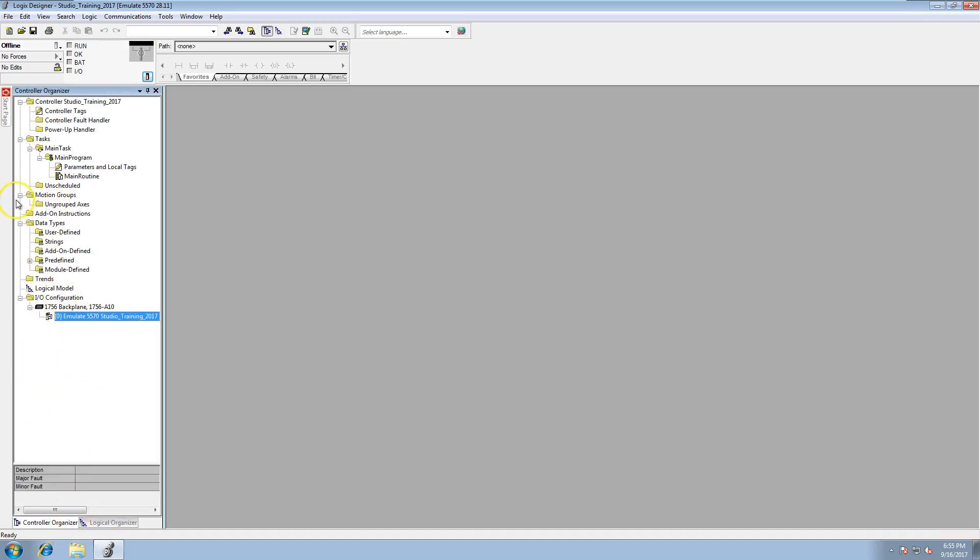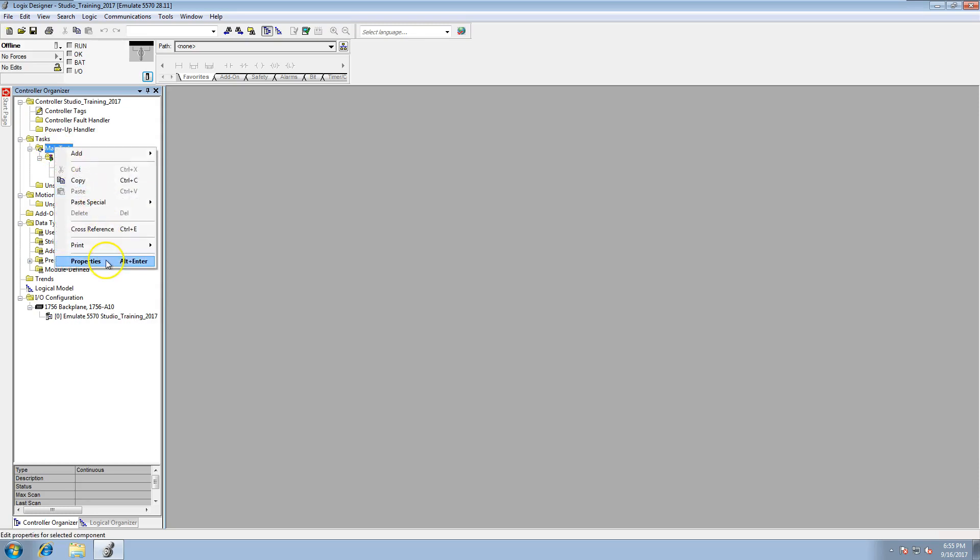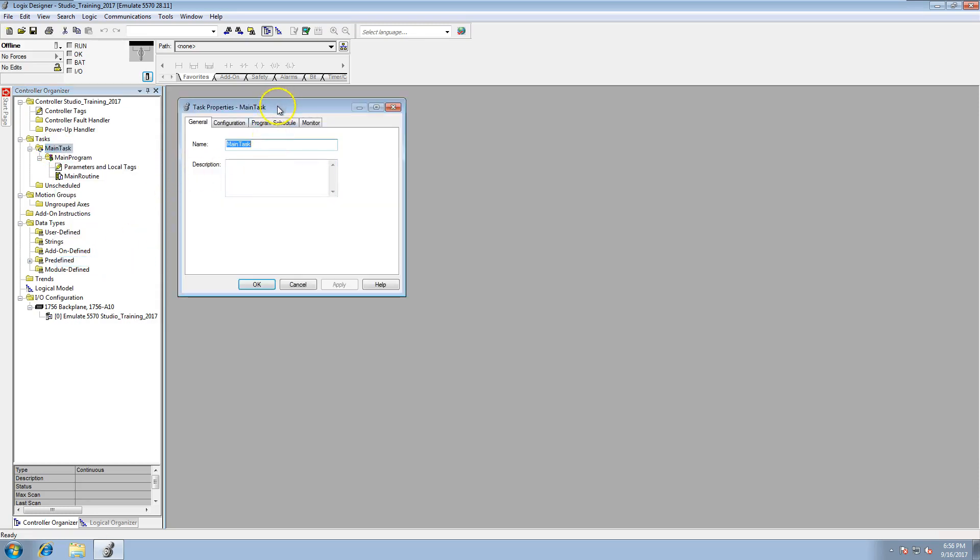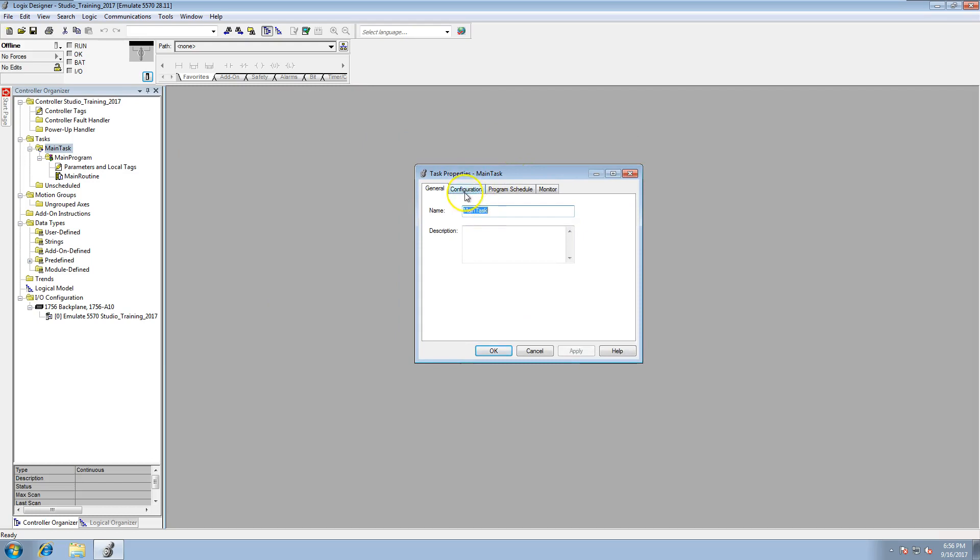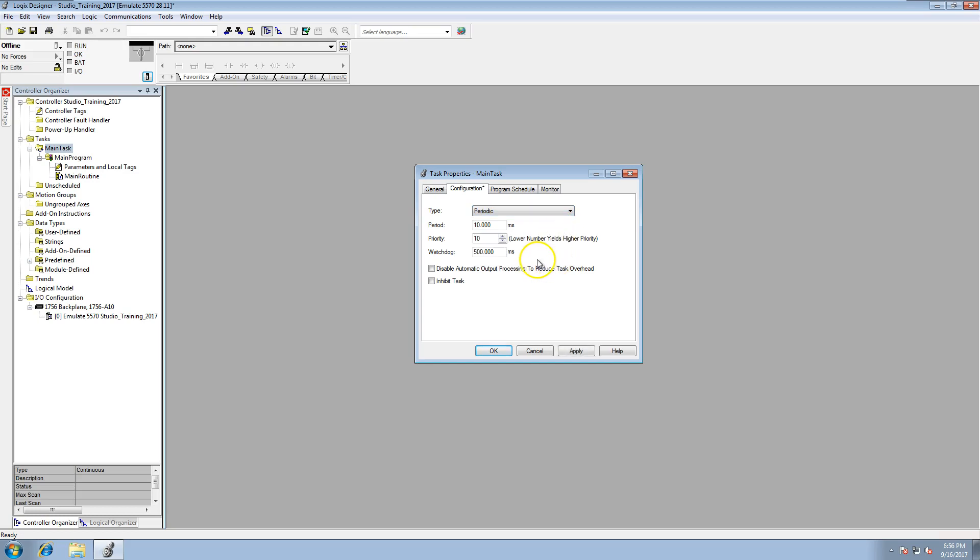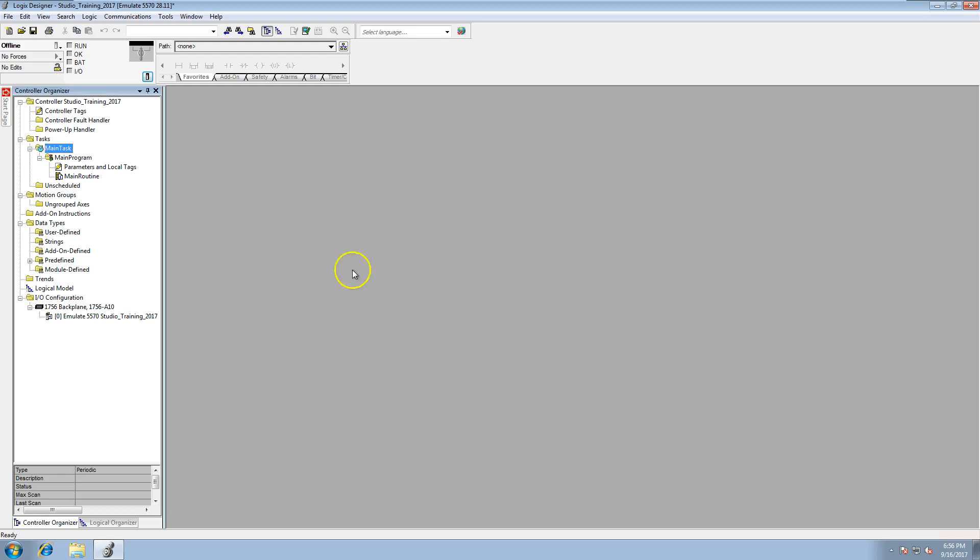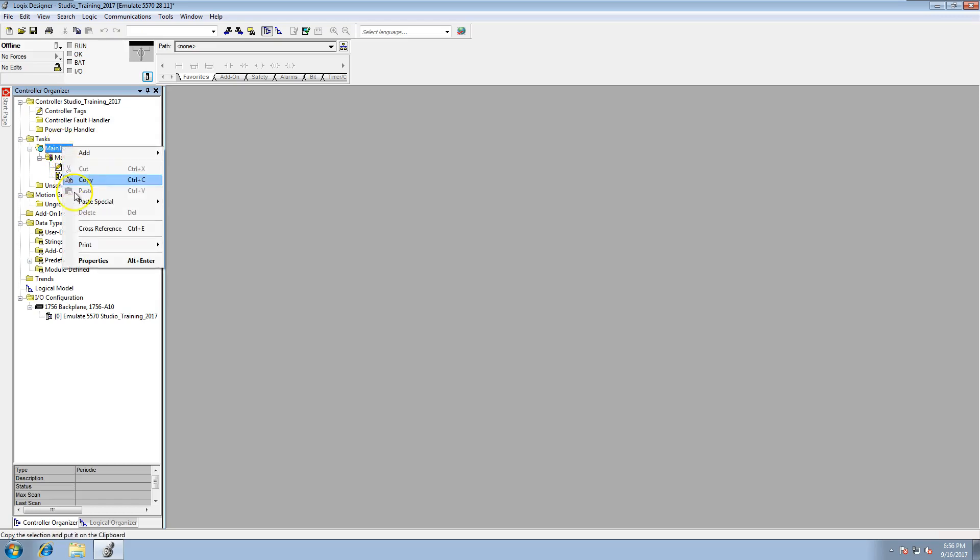This being the start of what we're doing, the first thing I like to do—being that this main task is a continuous task—I think it's been best practice for proper timing to go ahead and get everything in the periodic. So what we'll do is we'll put the periodic at 50 milliseconds, and we'll keep the priority, say, for instance, like a six. We'll hit Apply. At that point, we now change our main controller to a periodic task. At this point, I'll go ahead and tell you that the way this thing scans, instead of it scanning and using a scan of continuous, let's break that down a little bit closer for those who don't know.